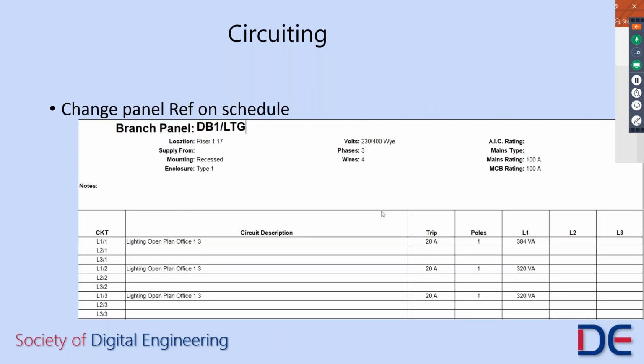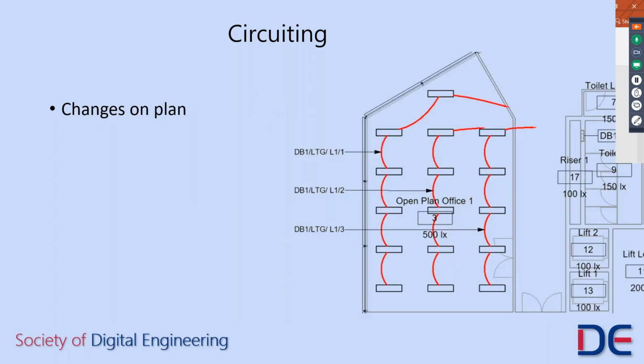But what if we want to change the name of the lighting board, which will change the circuit name for all of the circuits that are connected to this? So here we're changing it from lights to the more traditional LTG for a lighting board. If I change it on my panel schedule, it is then reflected immediately on the plan. And this can save hours and hours and hours of technician time.